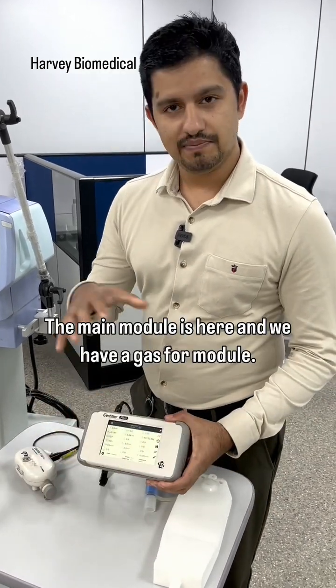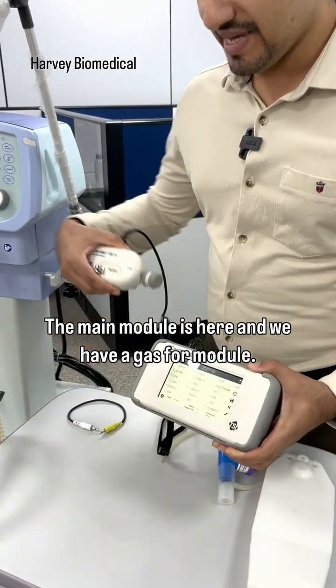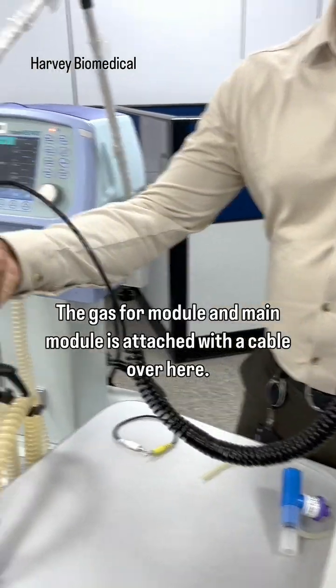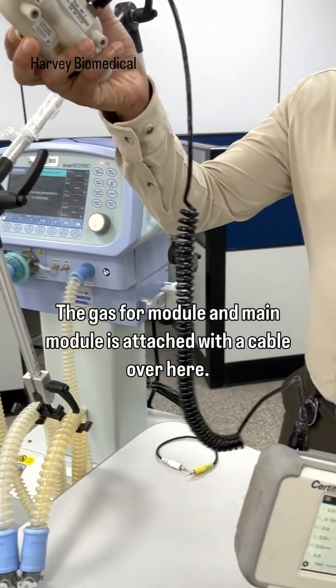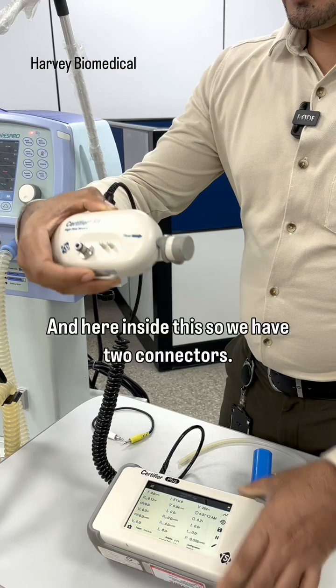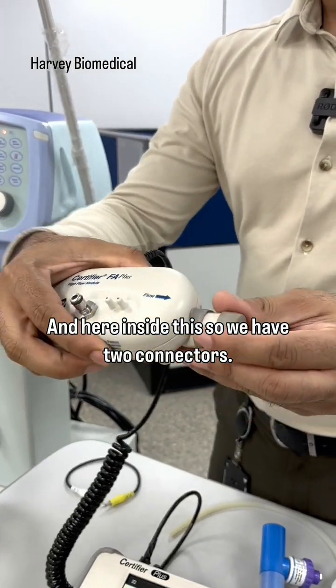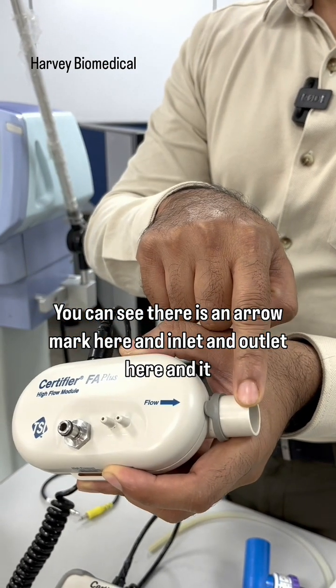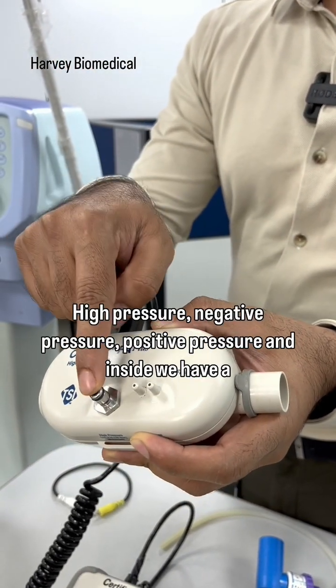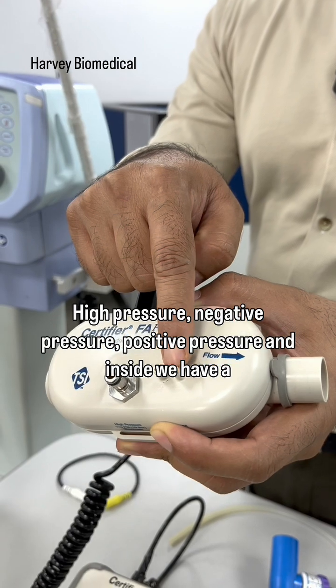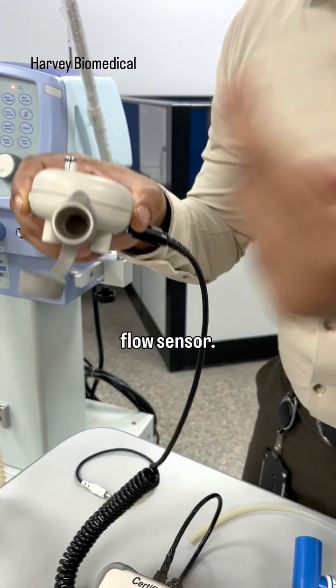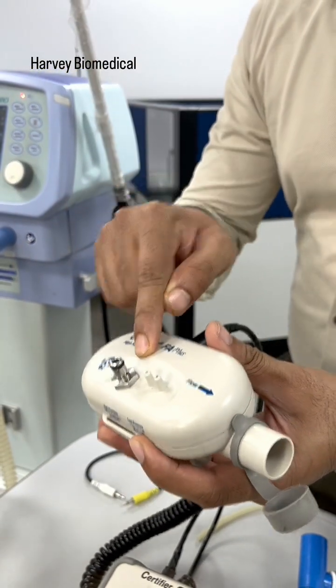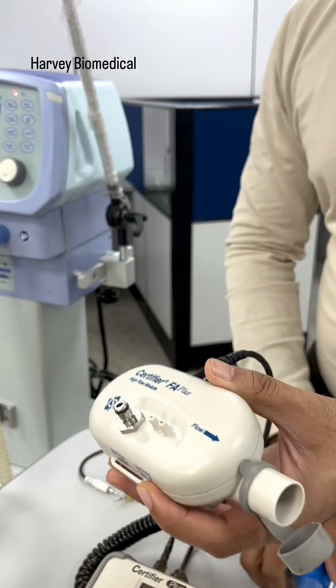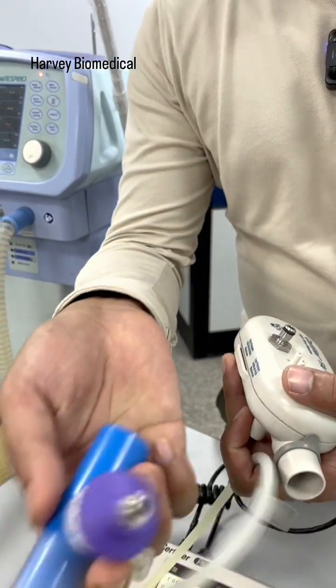Now we have two modules. The main module is here, and we have a gas flow module. The gas flow module and the main module are attached with a cable over here. Inside this, we have two connectors. You can see there is an arrow mark here, and an inlet and outlet. It has pressure sensors, high pressure, negative pressure, positive pressure, and inside we have a flow sensor. So mainly it has two things, pressure sensors as well as a flow sensor. Additionally, we have an oxygen sensor, which is a galvanic oxygen sensor.